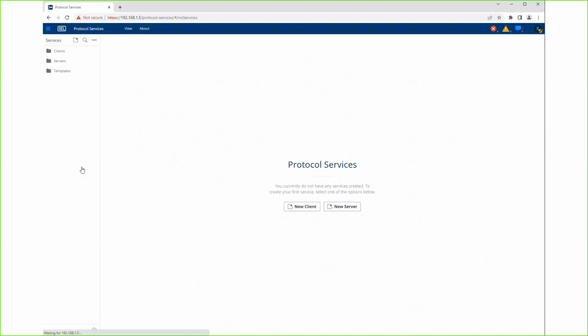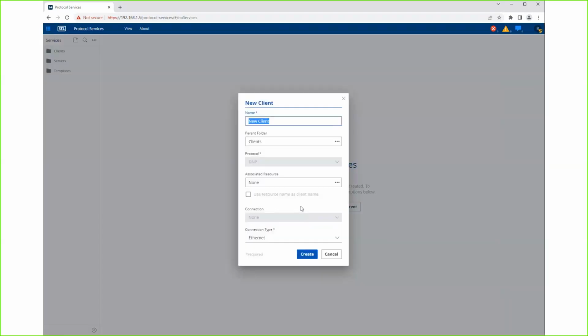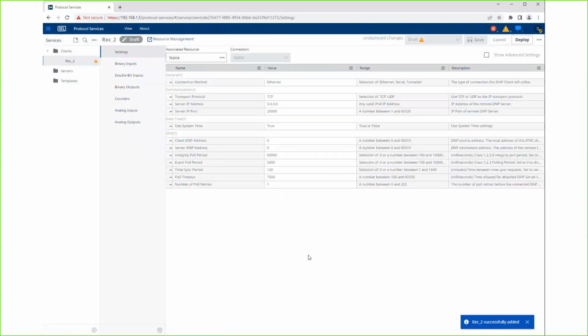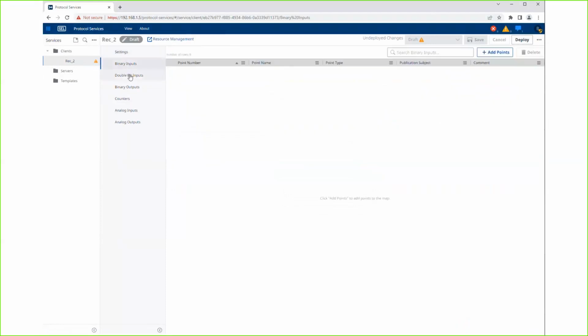So we go to another application called Protocol Services. Protocol Services is where you configure DNP in Blueframe. So what I'm going to do is make a new DNP client connection called Rec2 or Recloser 2. I would fill out my IP address and DNP settings here. I would configure my binary outputs and analog inputs, all the stuff you would expect for DNP in these tabs. But I'm not going to do that just yet.